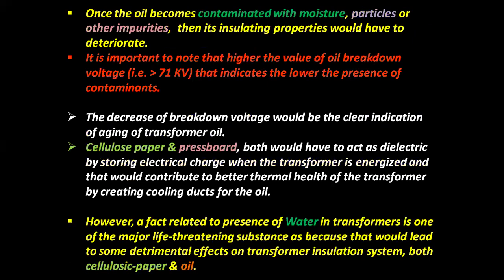Once the oil becomes contaminated with moisture, particles or other impurities, its insulating properties deteriorate. It is important to note that the higher the oil breakdown voltage, that is more than 71 kV, the lower the presence of contaminants. The decrease of breakdown voltage would be a clear indication of aging transformer oil.